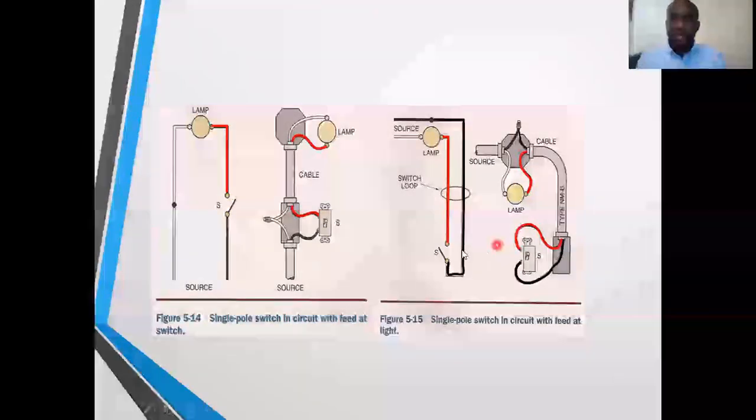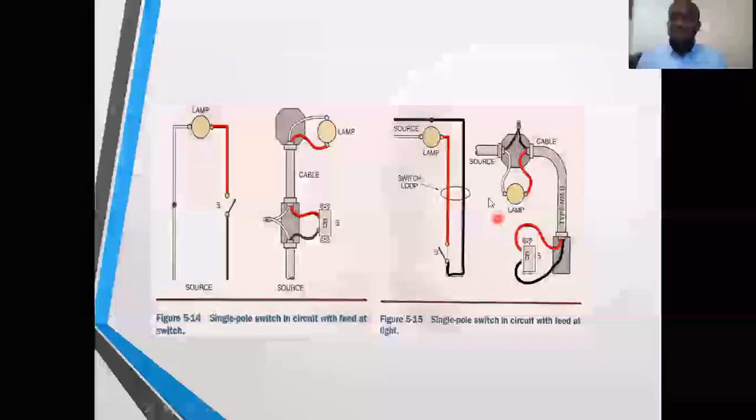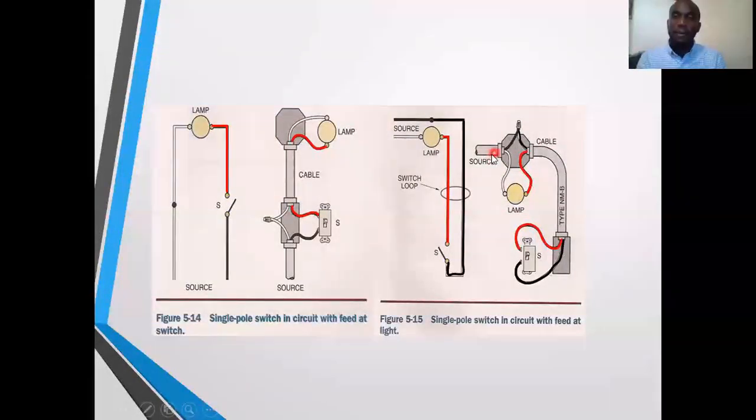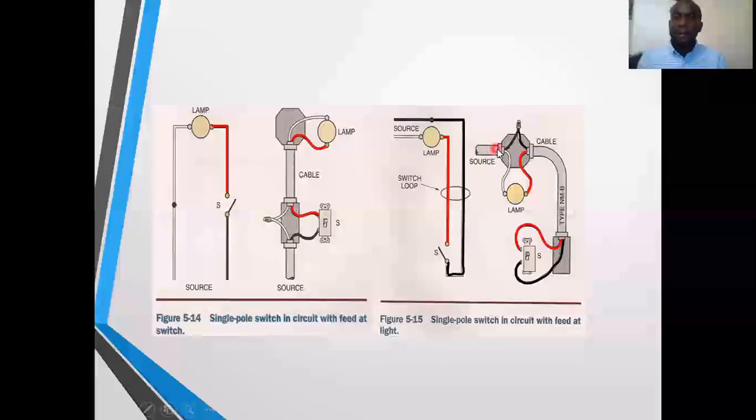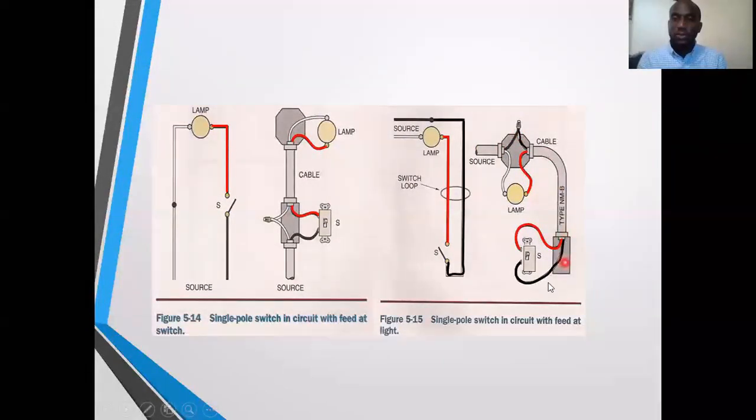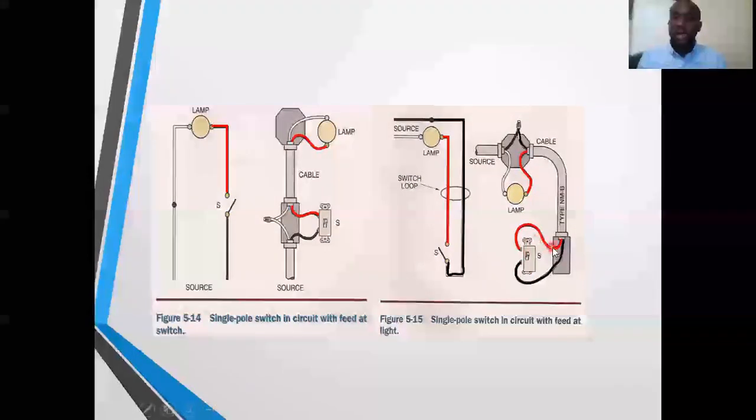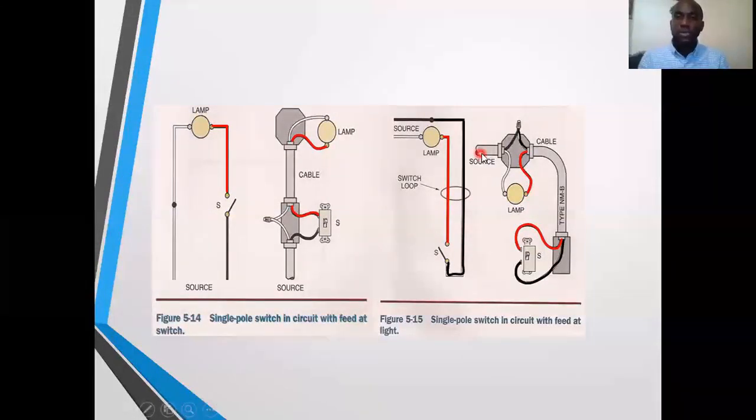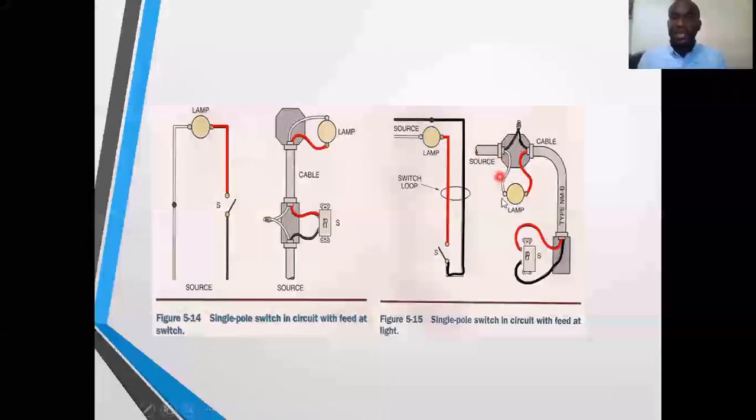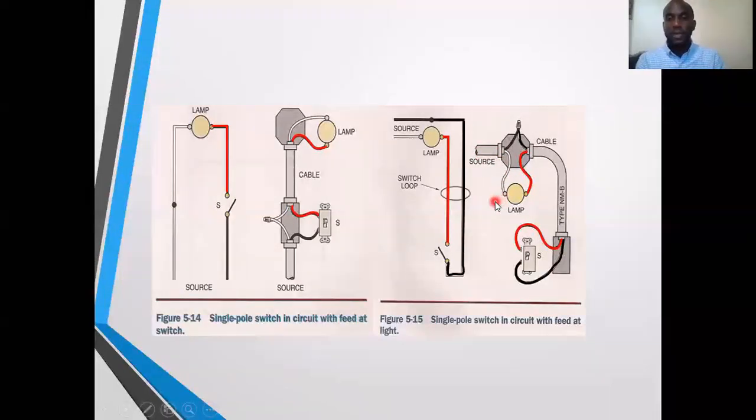At the lamp, we will bypass the lamp with the main black, send it to the switch. From the switch, we will take the red, tie it back to the lamp at the brass terminal. And of course, the source neutral goes directly onto the lamp.